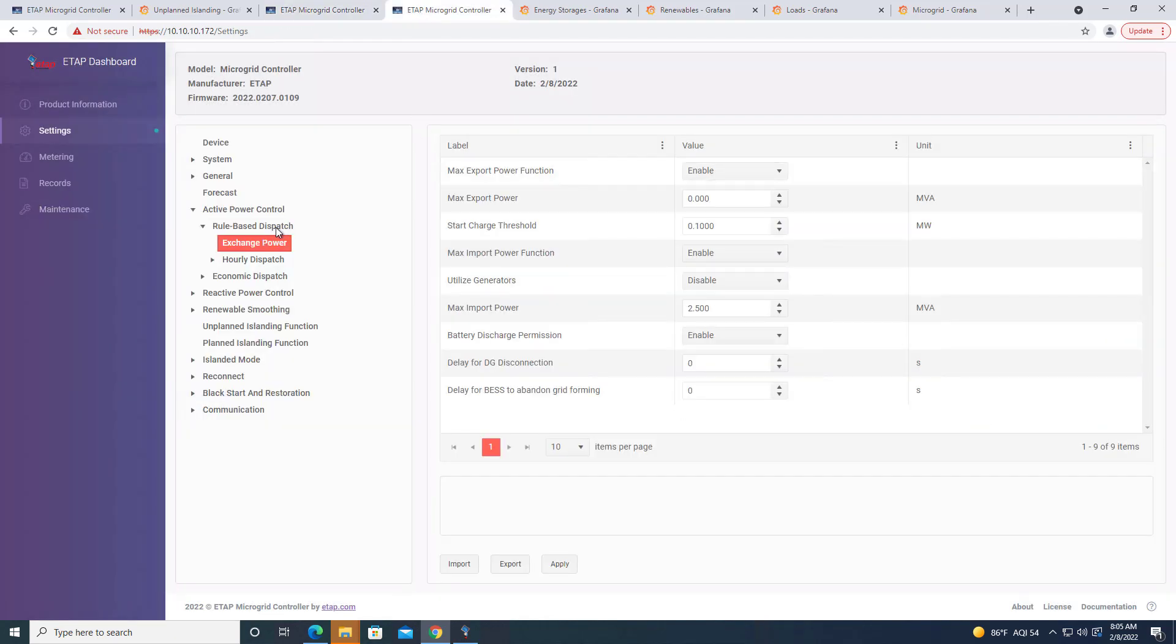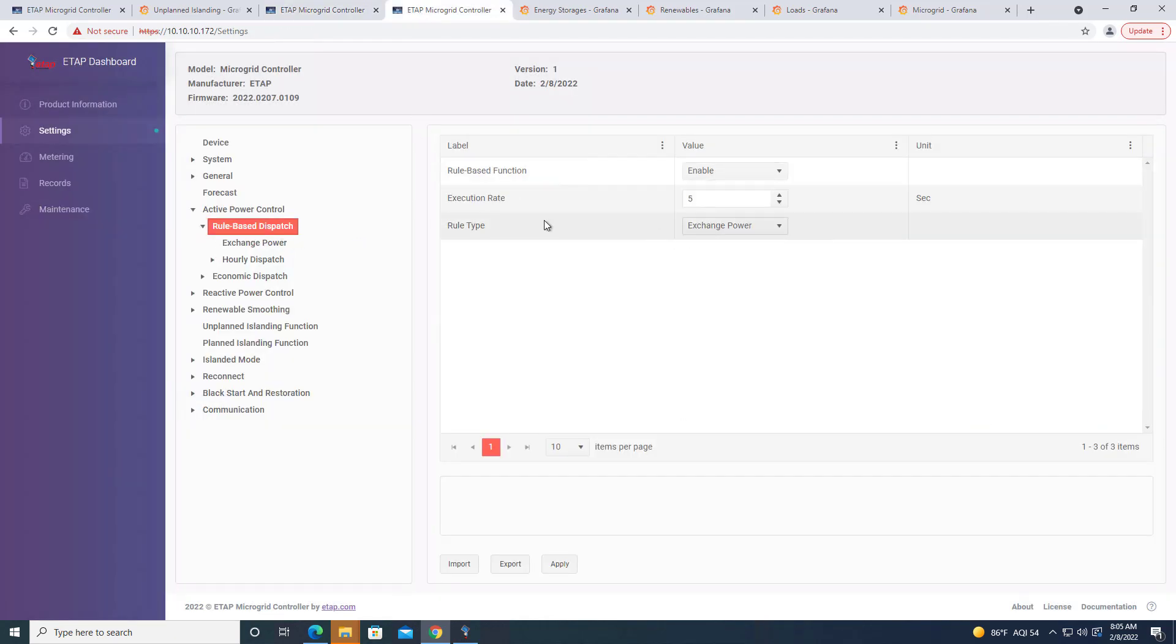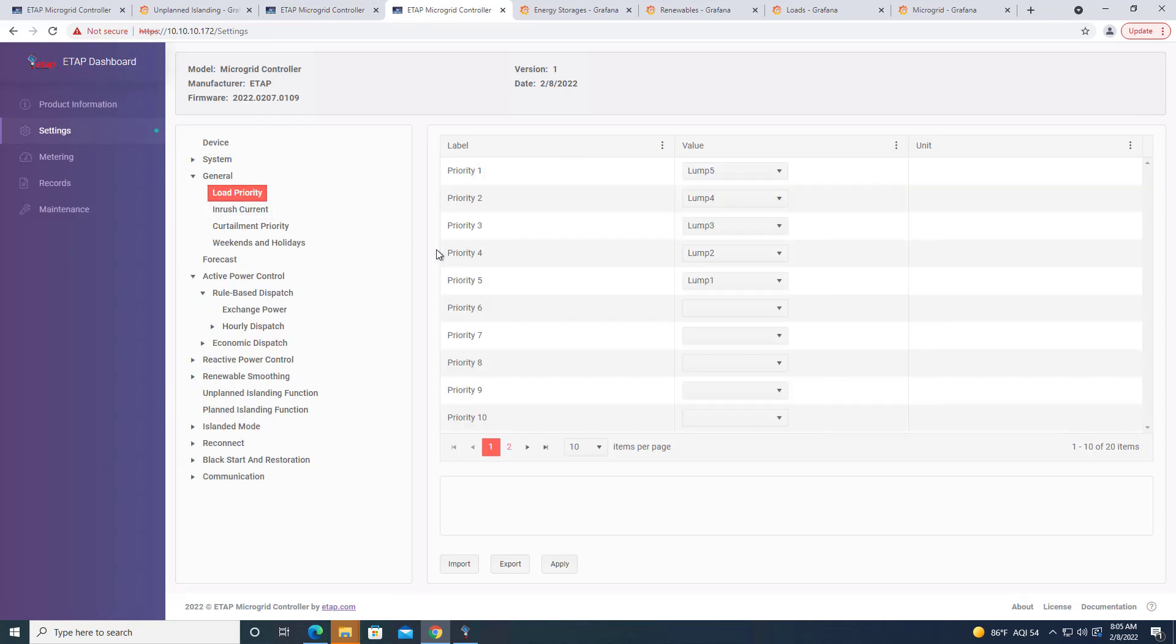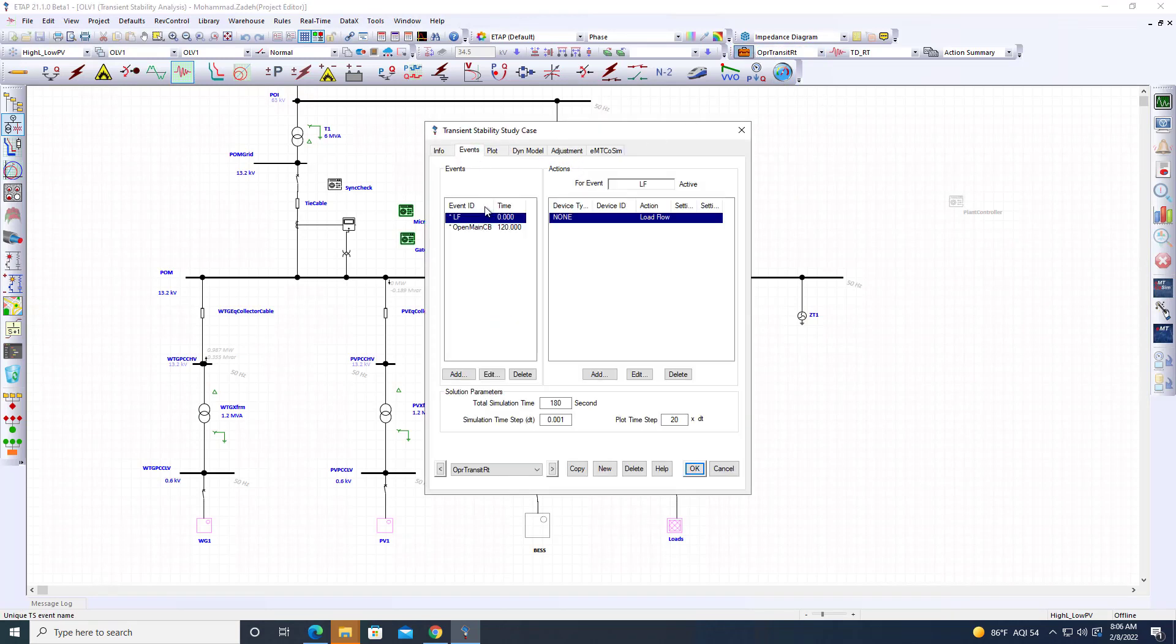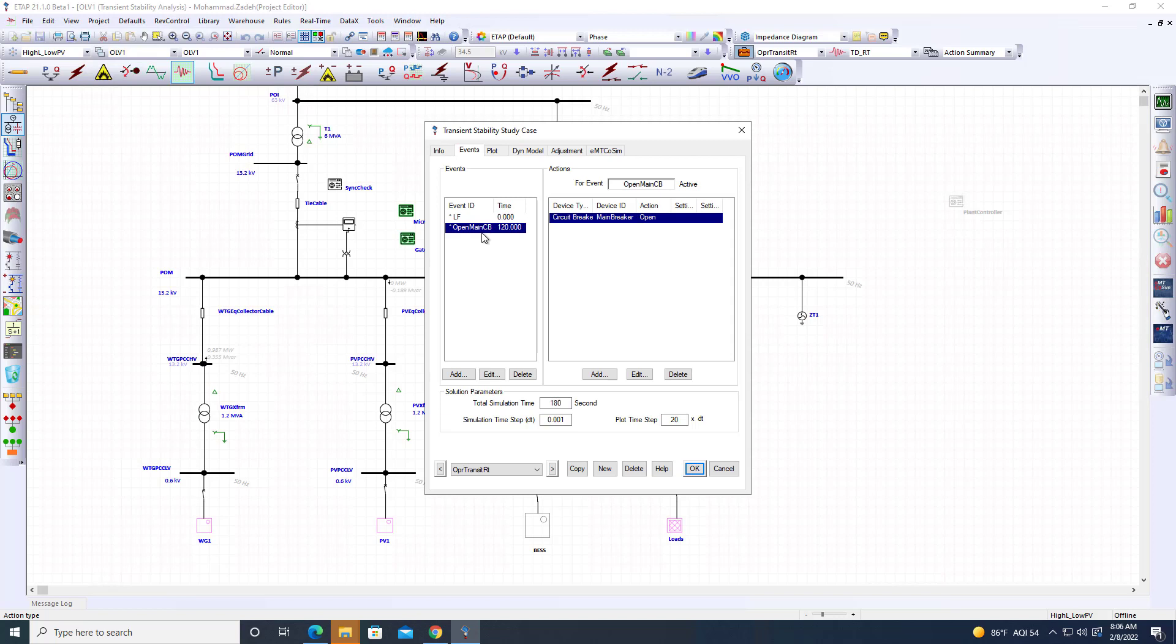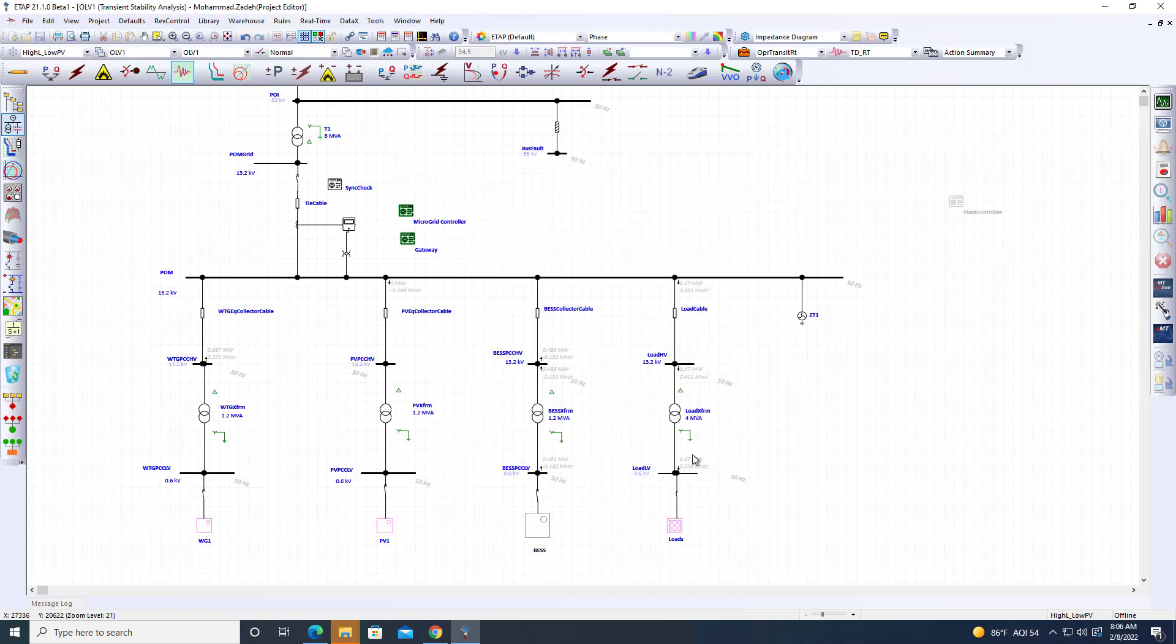You can go ahead and look at the settings of the microgrid controller, different settings that we have here. Now once that's done, let's come back here. I've created a study case with a little bit longer simulation time, about 180 seconds. I want to give more time to be able to go on the real-time side and go through the different dashboard and see how it works. But after two minutes, 120 seconds, we have an event to trip the circuit breaker at the point of interconnections.